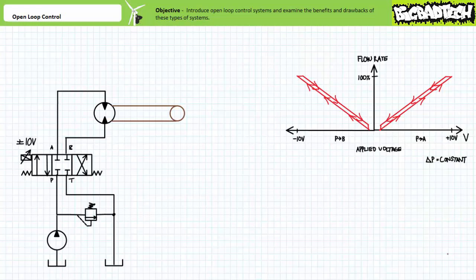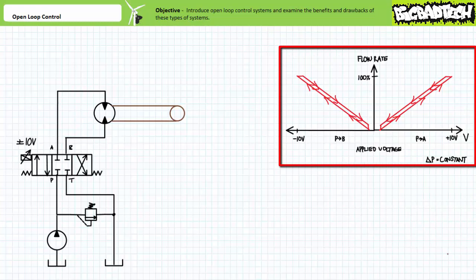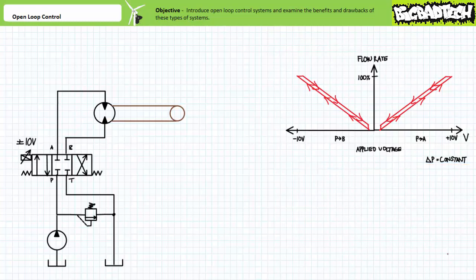Let's assume this proportional valve makes use of a bi-directional linear force motor, where voltage magnitude influences spool displacement magnitude and voltage polarity influences spool displacement direction. Assuming the linear force motor is operational inside a range of positive to negative 10 volts, positive 10 volts fully displaces the spool to the straight-through position, and negative 10 volts fully displaces the spool to the cross-connect position. Assuming relative linearity and only a small dead zone in hysteresis, intermediate magnitude voltage signals would produce proportional — hence the name — intermediate flow rates, as this graph of flow rate as a function of applied voltage suggests.